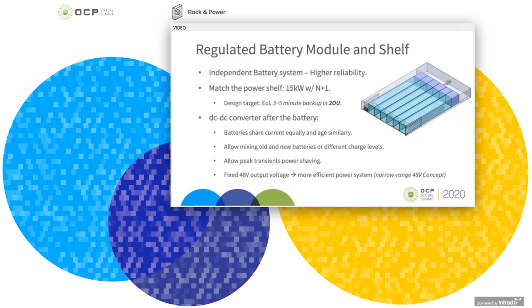Here you can see some rack power configs based on the solution we presented. As we said before, the solution is completely flexible, so any customer can configure it in the way that meets their demand best. The picture on the far left shows a rack with only one U shelf, giving you 15 kilowatt at N+1, with no battery backup if you don't want it. The second picture shows a rack with a power shelf and battery shelf, 1U power shelf and battery shelf. You can get 15 kilowatt at N+1 and have backup time as well. The position of the power shelf or battery shelf can be anywhere in the rack.